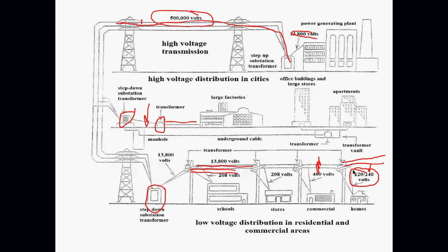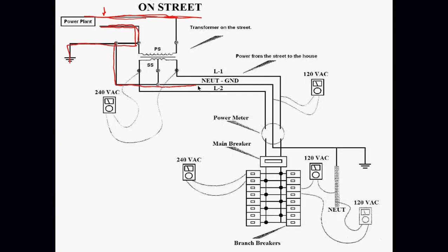Once you come in from your street, you have a hot leg. Okay, up at the top, you have your basic neutral. So you have one hot wire. This is the one at the top of the pole. You have one neutral. That's also grounded. Okay, that's an earth ground. That neutral comes into your breaker panel, and goes to a neutral bar. That's on one side of your panel. Notice it's also grounded. You see how many times this neutral is grounded?